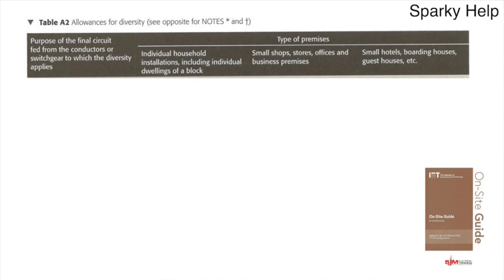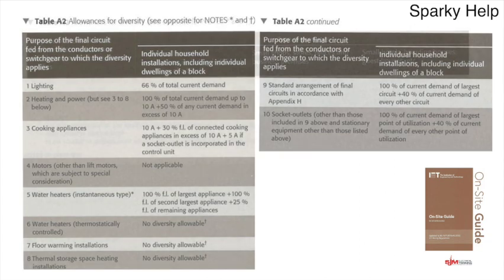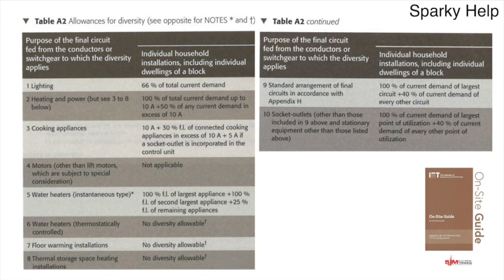The On-Site Guide breaks it down by type of property and circuit. It covers household, small shops, and small hotels — you pick the best description. Remember, the On-Site Guide only covers installations up to 100 amps, whether single-phase or three-phase. For individual household installations there are 10 circuits listed. Lighting, for instance, is 66% of the total current demand — meaning 66% of the lights are assumed on at any time, which is quite generous. Heating and power has sub-categories for items like cookers, motors, water heaters, thermostatically controlled, instantaneous, underfloor warming, or thermal storage, with: 100% of total current demand up to 10 amps, then 50% of any excess over 10 amps.